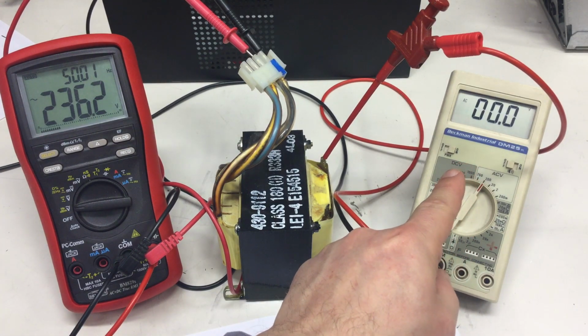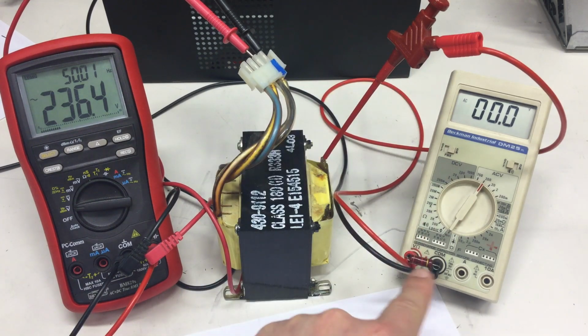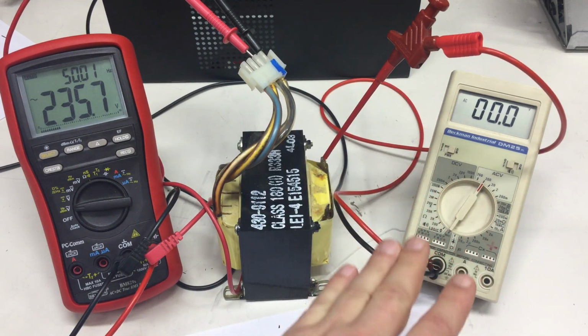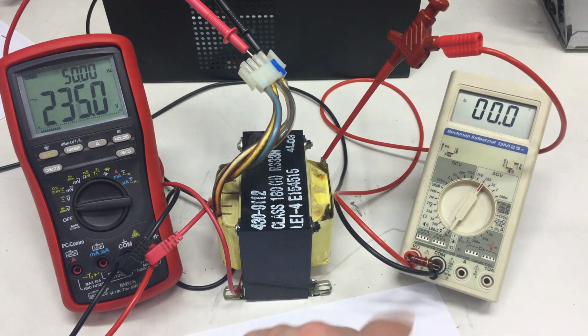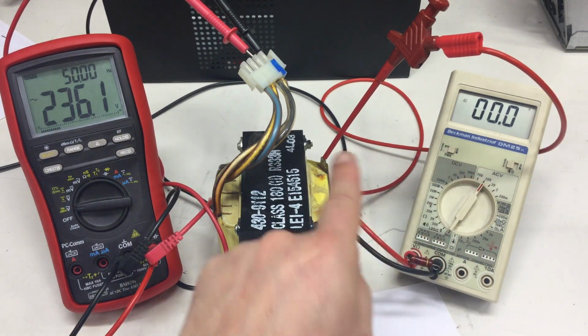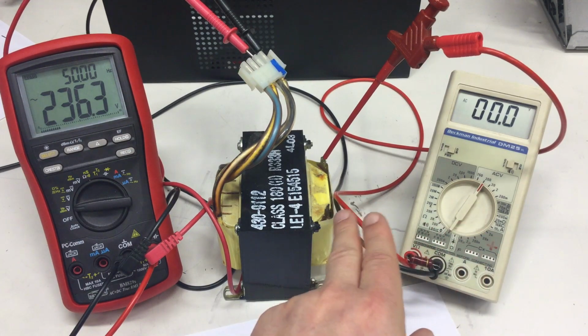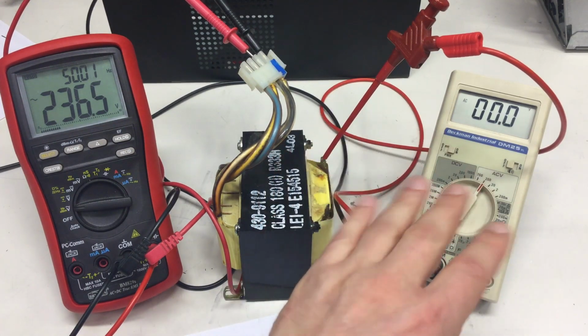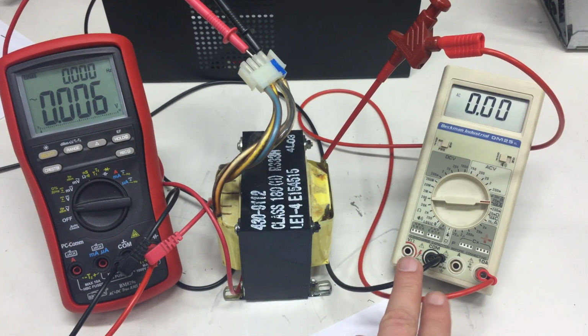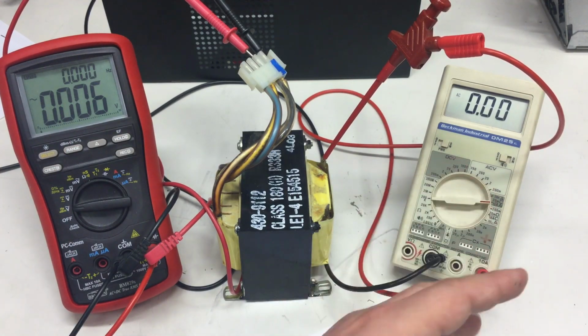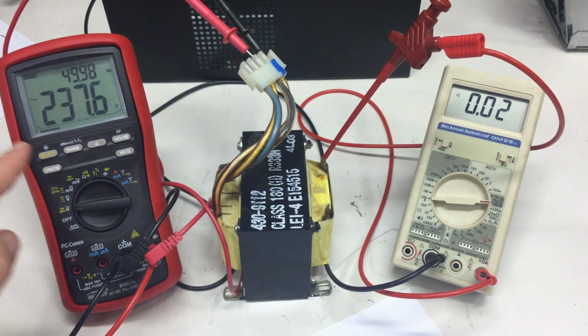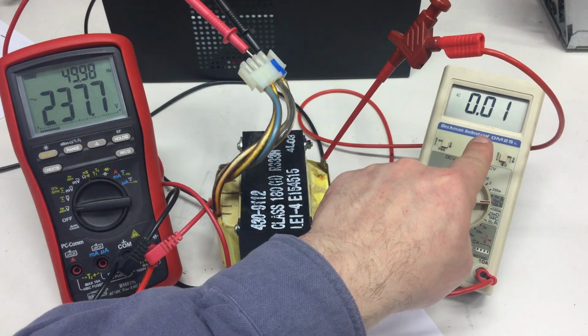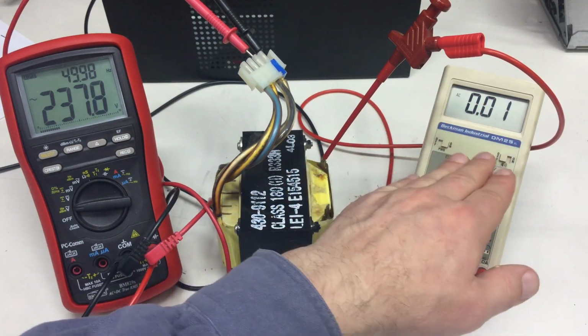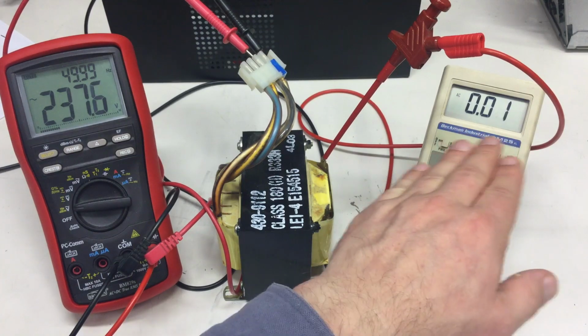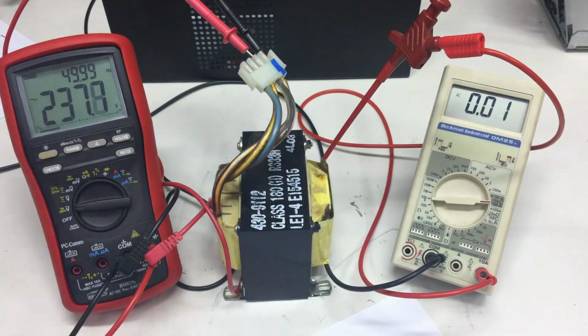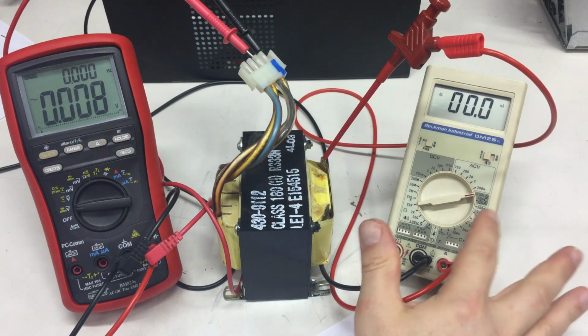Voltage gone. So, and a 1K load. And yeah, the final test, we measured the current that is actually flowing from secondary to mains earth on a short. Yeah, starting in the 10 amp range, just to be sure I'm not killing something. Power. And there is something displaying that could be interpreted as 10-20 milliamps, but it's not. 200 milliampere AC.